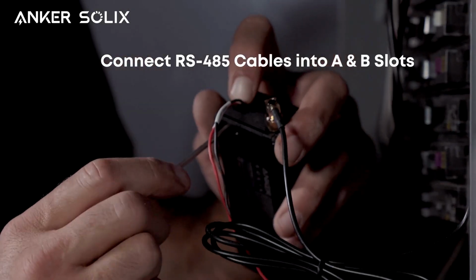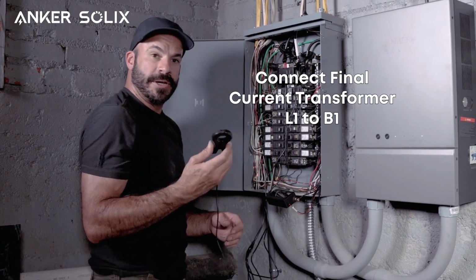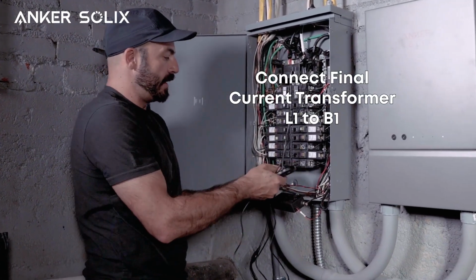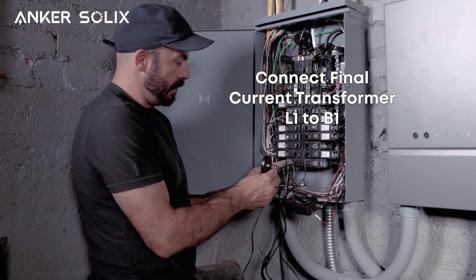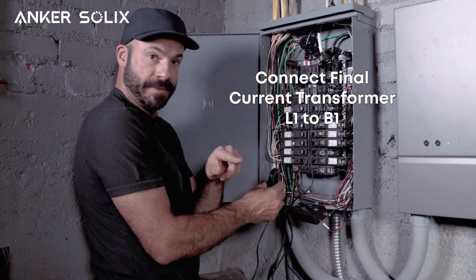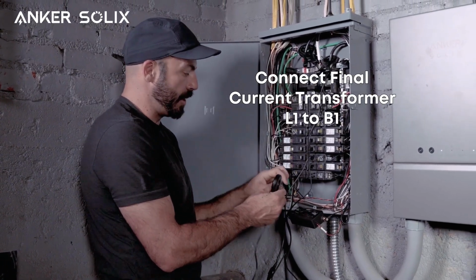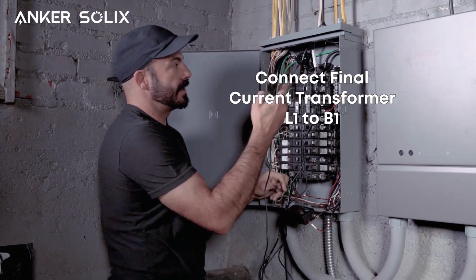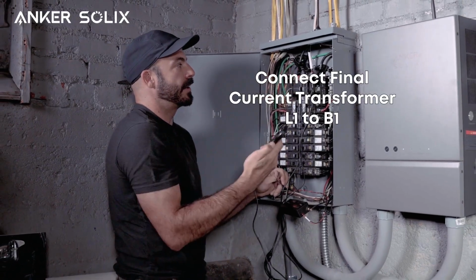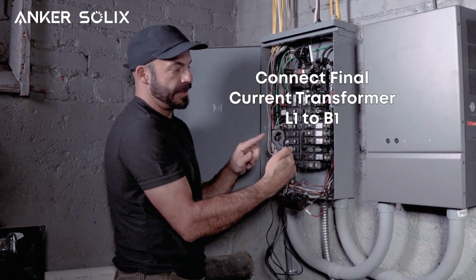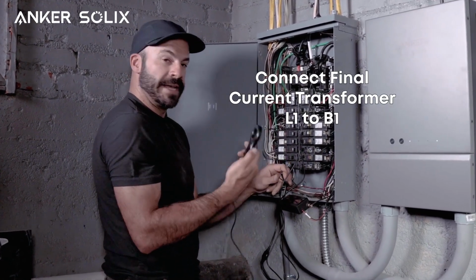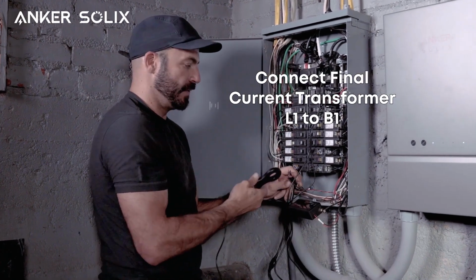Now we'll connect the final current transformer around a loop of wire that I left when I connected our branch circuit for the bidirectional inlet box to the breaker here. Since this is on our L1, I'm going to connect it to the B1 current transformer. Again, you want to make sure you get the orientation of this correct.